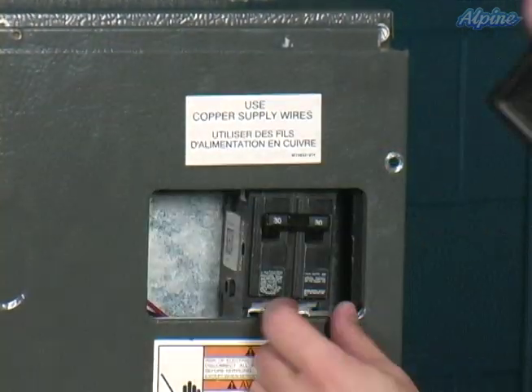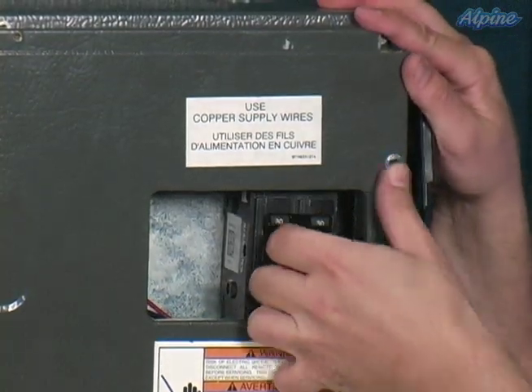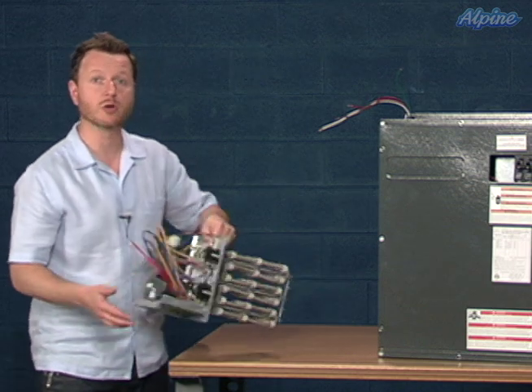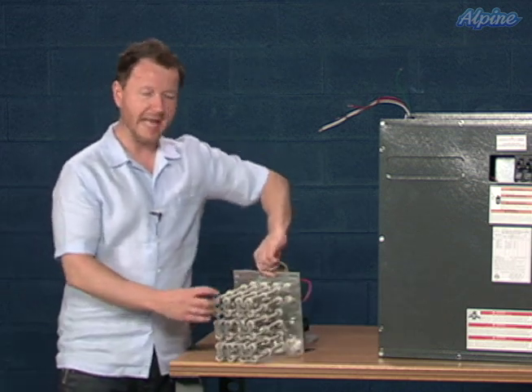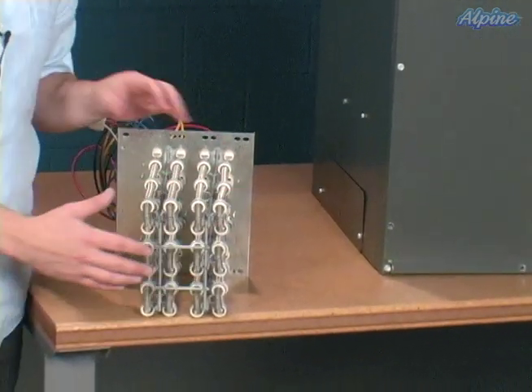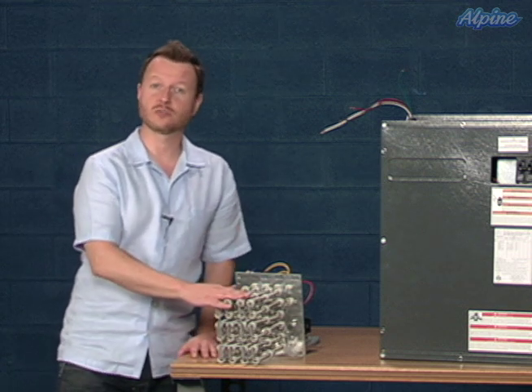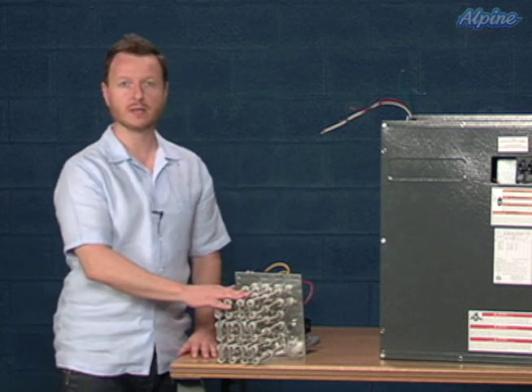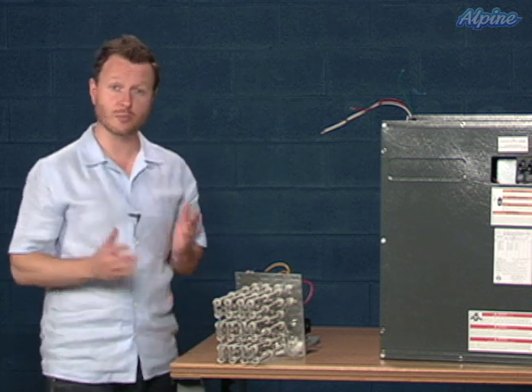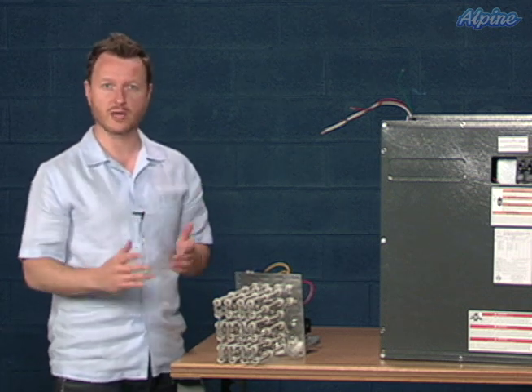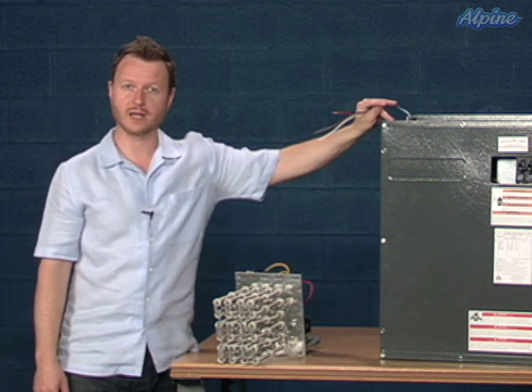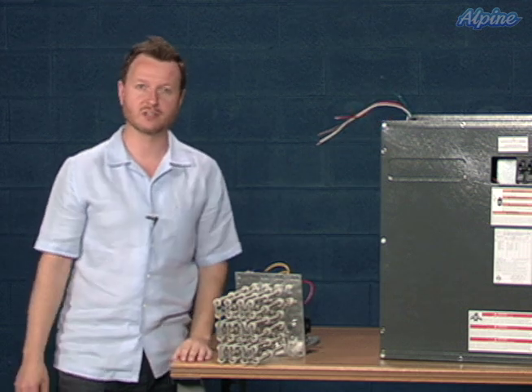This pops in place and that allows you to access the breaker to turn the unit on and off. Some of the larger electric heater coils can be operated in multiple stages, meaning only half of the elements will come on if just a little bit of heat is needed. If more heat is needed, then the other half will come on additionally for full heat capacity. A larger heater coil, such as a 20 kilowatt, is capable of doing that. You would simply need to have a multiple stage heating thermostat, which will know when to turn on what half. And depending upon how that thermostat is connected to the low voltage wiring on the equipment, it will give you that multi-stage capability.